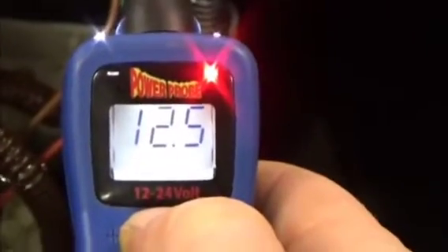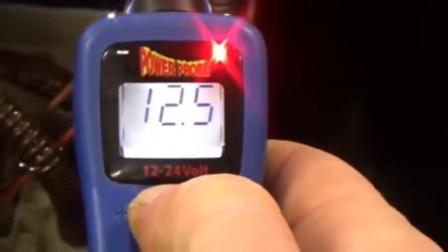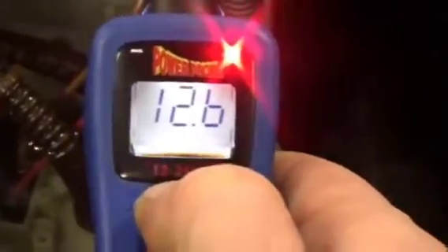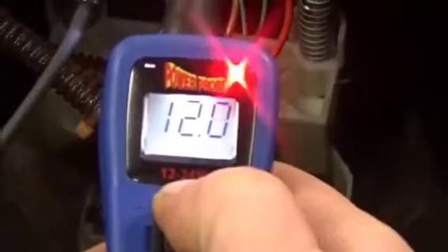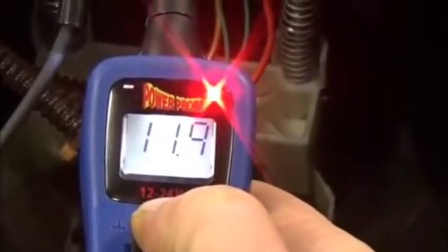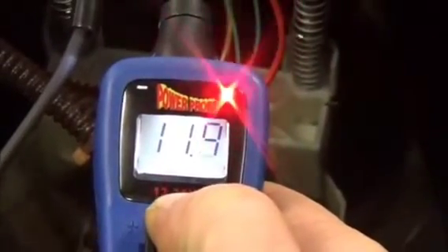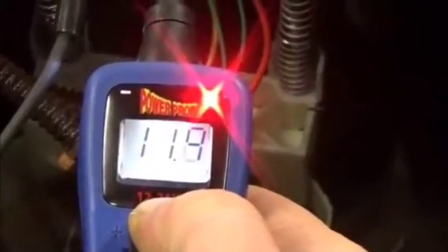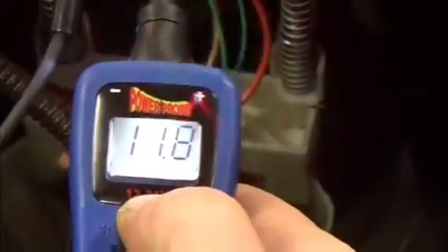That shows the supply voltage we have available. Now when you engage that, go ahead and do it on the pump again. That flickering light is not good, that would indicate a bad connection or maybe even under load, poor insulation on the wire. We want a solid red light when doing load testing.